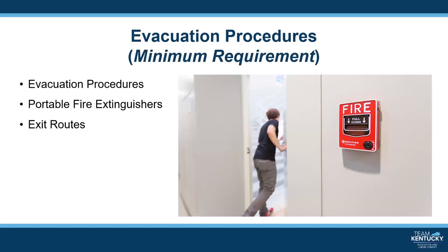Evacuation policies, procedures, and escape route assignments are required to be in an emergency action plan. They are put into place so the employees understand who is authorized to order an evacuation, under what conditions an evacuation would be necessary, how to evacuate, and what routes to take. Exit diagrams are typically used to identify the escape routes to be followed by employees from each specific facility location. It is important to note that when developing evacuation routes, the map should notate all potential routes instead of telling a certain area to evacuate through a certain route. This is because it is impossible to predict where the fire or other event may occur. Employees should be instructed to exit through the closest and safest exit.